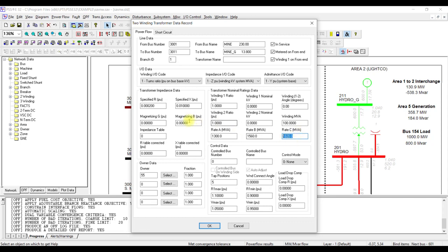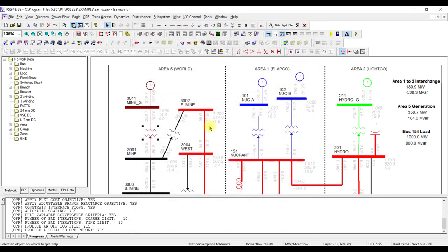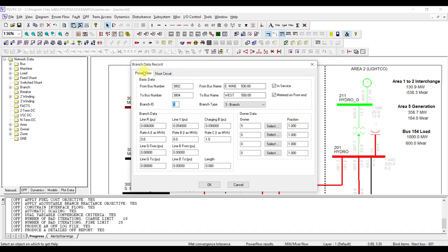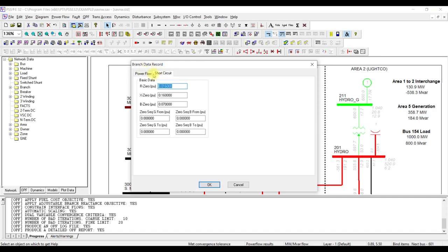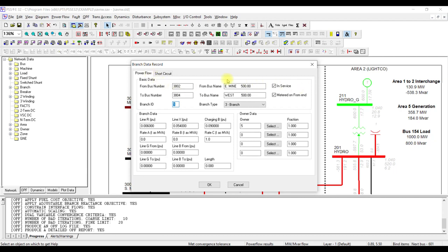This is how we model the transformer. Similarly, for the transmission line — double-clicking on the transmission line opens its dialog with the same Power Flow and Short Circuit tabs. For power flow, the from/to bus fields are filled automatically when you model the transmission line through the SLD. What we require is Line R, Line X, and Charging — the series components and shunt component of the line. The same Rate A, Rate B, and Rate C apply for the MVA capacity of the line.